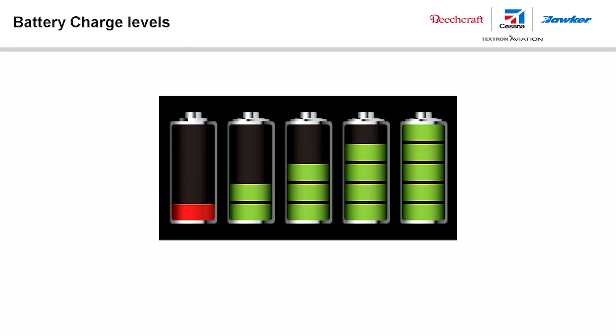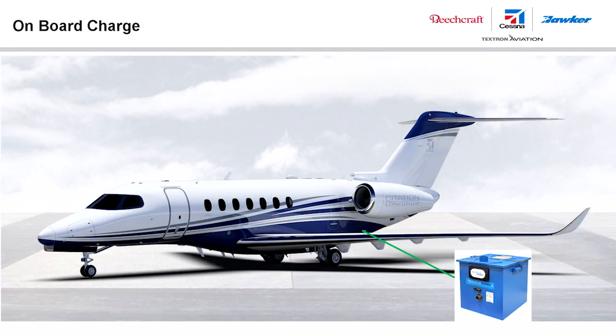If the battery's voltage gets low, it may indicate that all 19 modules have gone offline. Whenever a cell in a module falls below its minimum voltage of 2 volts, the module will disconnect from the battery terminal. The CMS is powered from the battery terminal, so when the battery voltage falls too low, the CMS will not be active until connected to an external power source. A battery with an open circuit voltage of less than 20 volts can be susceptible to electronics damage. Always use the deep discharge recovery charge procedures to restore the battery.